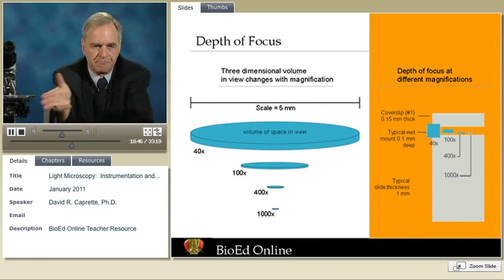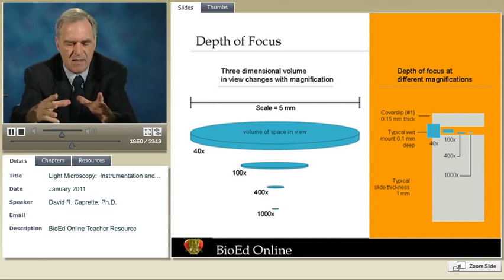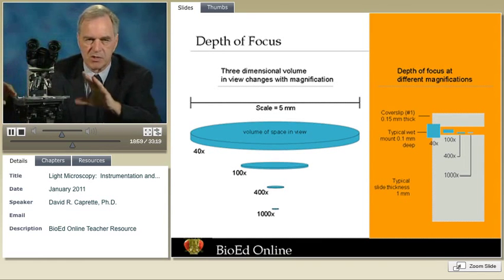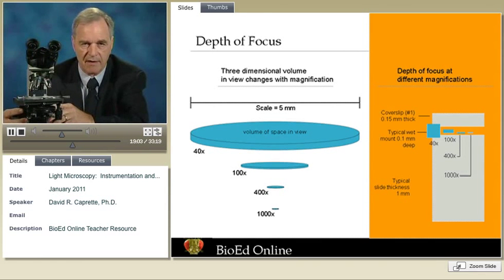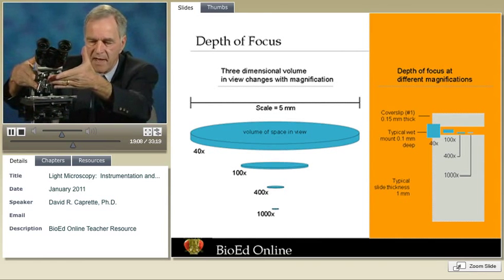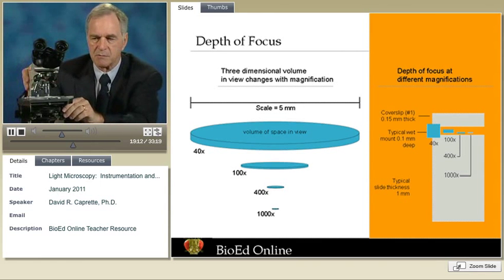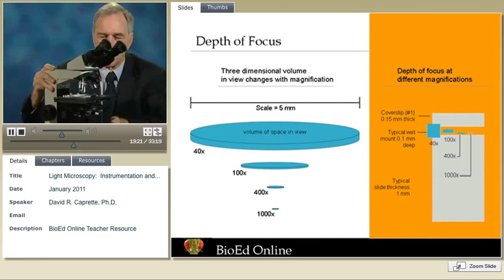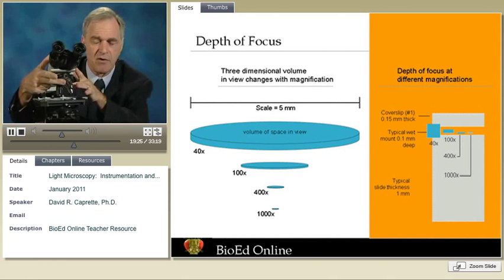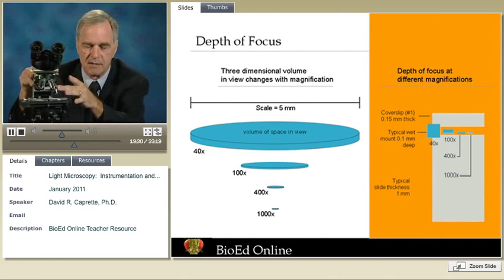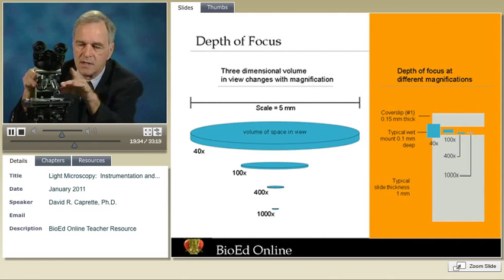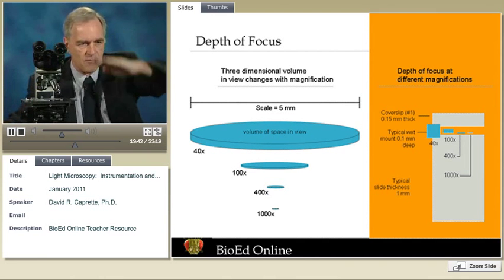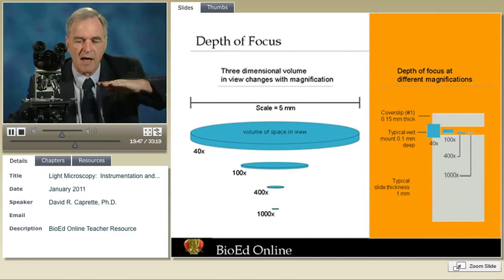It's depth of focus, not so much the XY plane, that gives us a headache when trying to find small specimens. The trick is to start at low magnification, focus on the specimen or on the surface of the slide, center it with your mechanical stage, work your way up in magnification, again focus, again center up your specimen, and continue to the highest magnification required. In a well-designed microscope, most objective lenses are parfocal — meaning when you're in focus with one magnification and switch lenses, you'll be very close to focus with the next, needing only a few nudges up and down.